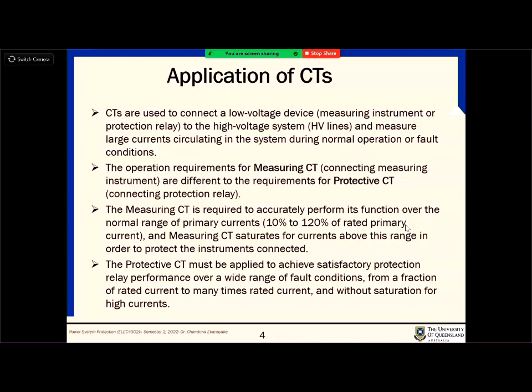And usually, when the load current goes beyond the 120%, these measuring CTs go into saturation, like every CT will saturate at one level. You can't have a CT which will never saturate, right? CTs will saturate at a certain level of current. But regarding the measuring CTs, since you are not interested in measuring the high current magnitudes, they usually go into saturation after 120%. That helps to protect the secondary circuits as well.